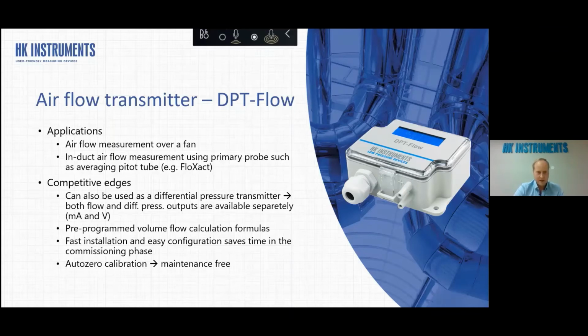And the competitive edge we have there is that you can use it also as a standard differential pressure transmitter or for airflow. So it's kind of versatile. If your applications are divided sometimes to airflow and sometimes to just the pressure, you can just stock this one yourself. And you can also freely configure the outputs with the jumpers for milliamp or voltage.